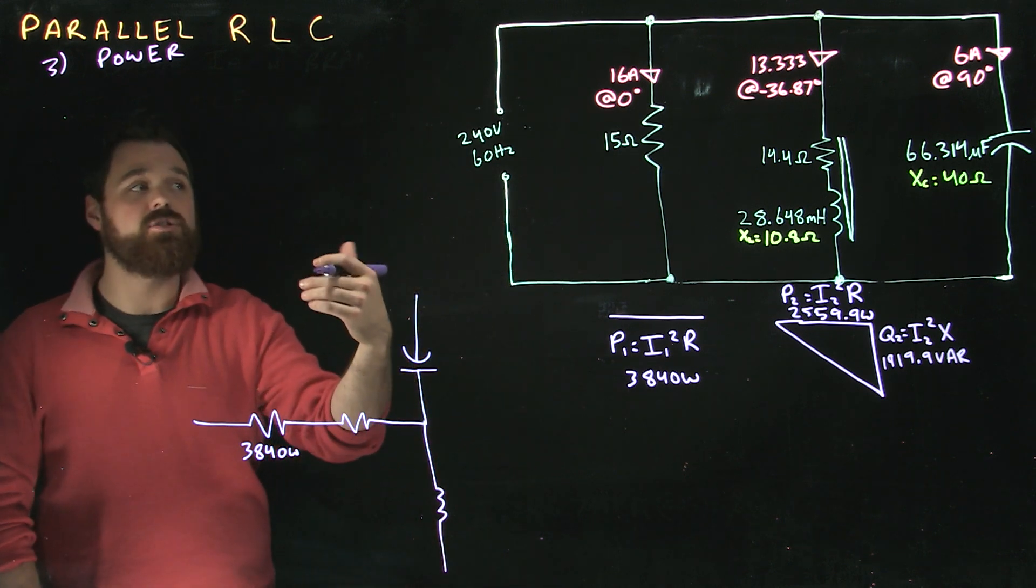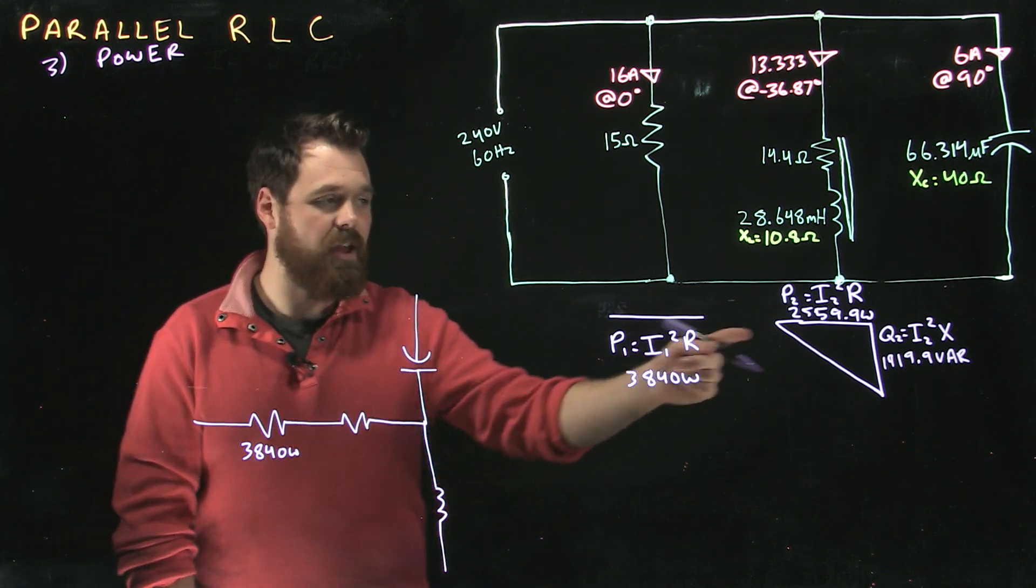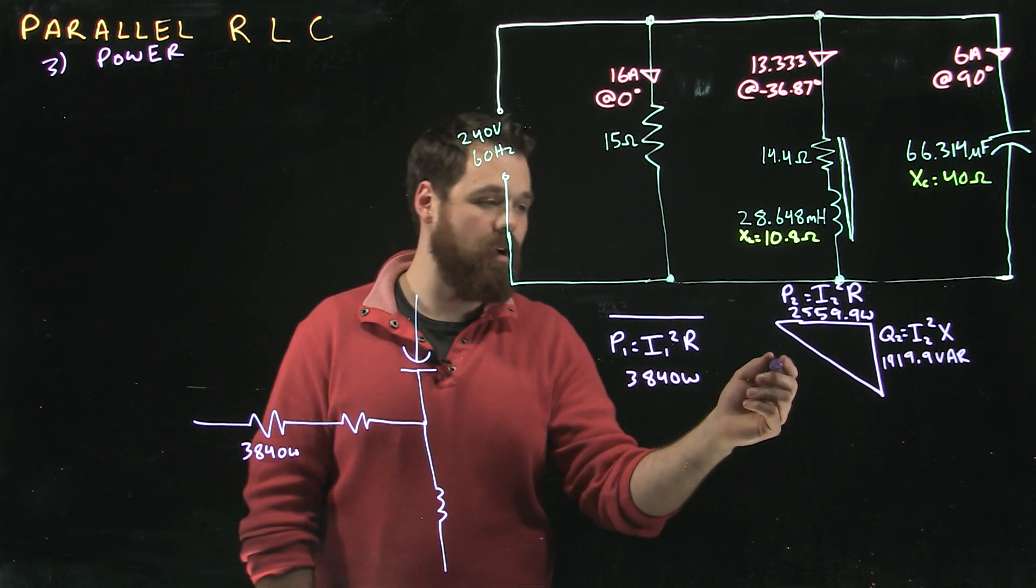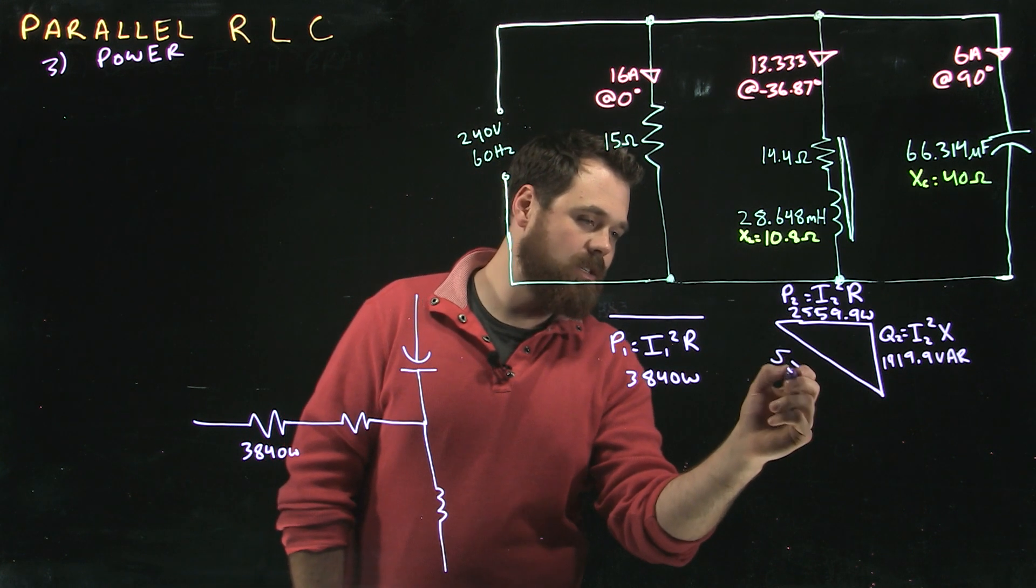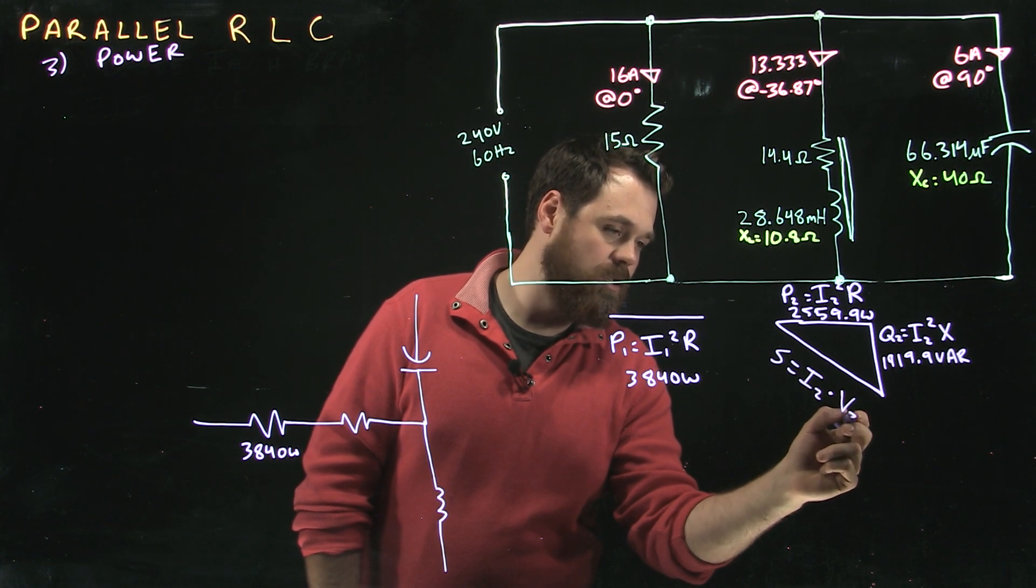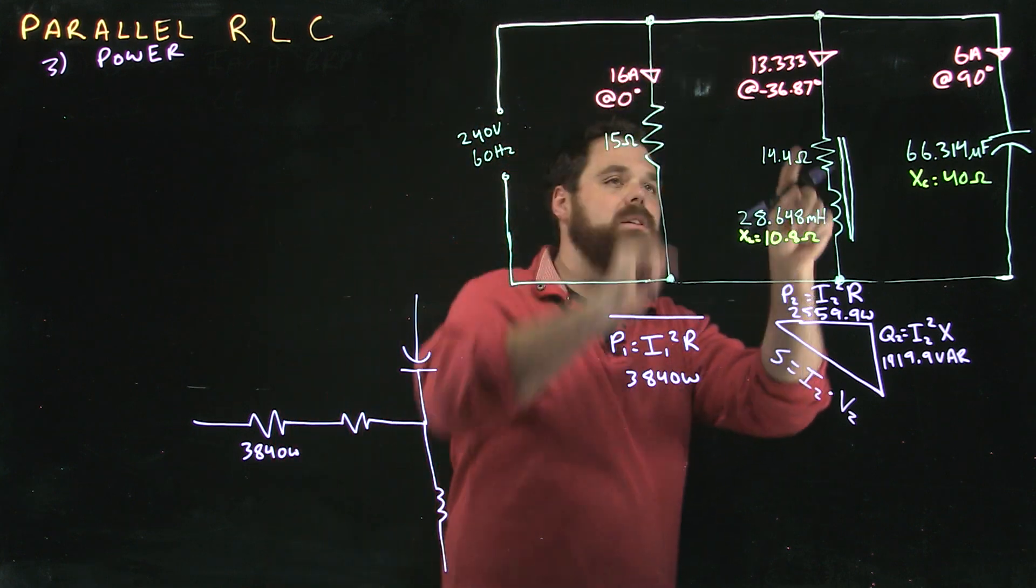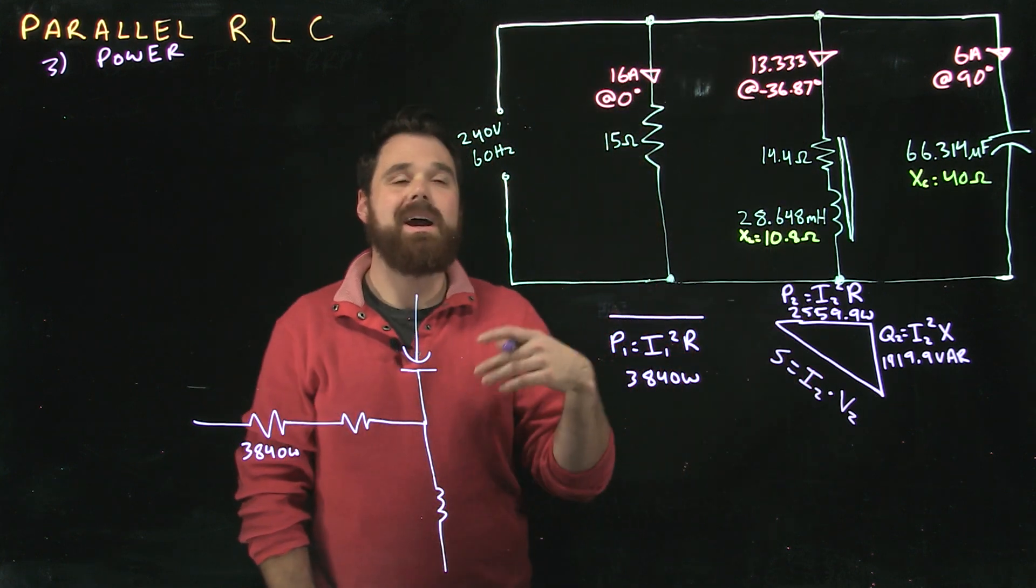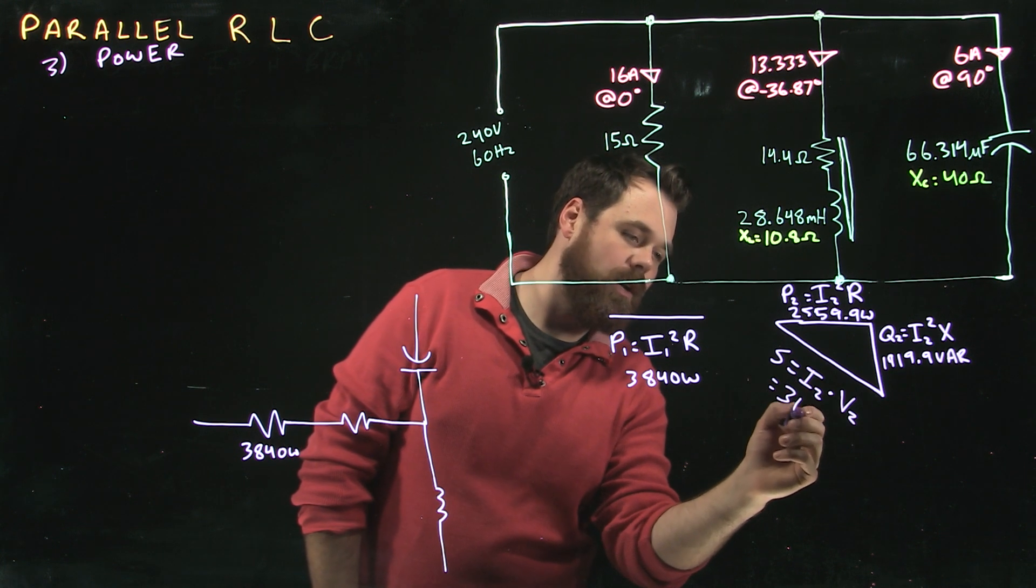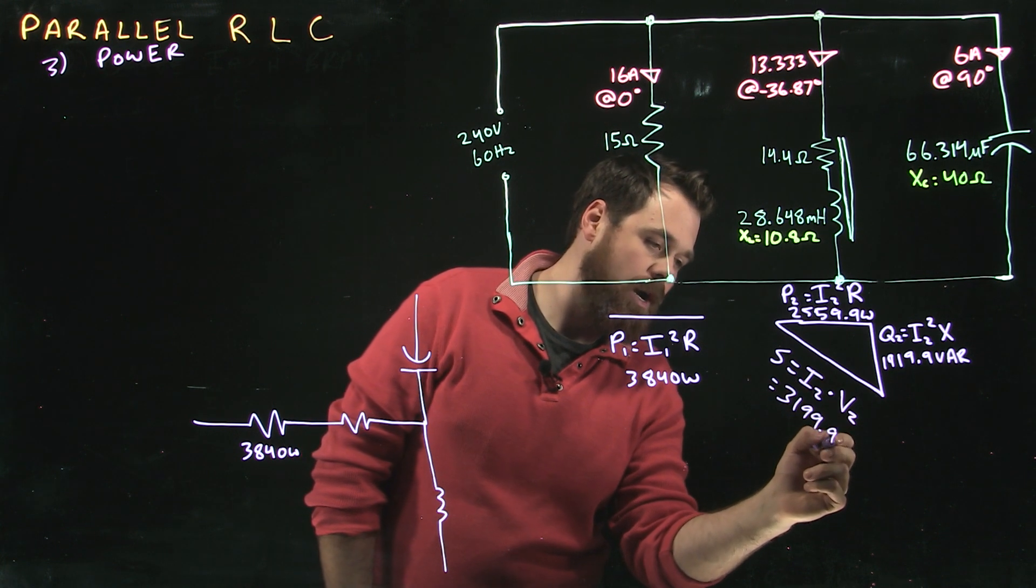Now, two ways from here. I can do some Pythagorean's Theorem. Q squared plus P squared equals S squared. Or I can go S equals I2 times V2. 240 volts times 13.333 amps. Either way, I should come out around 3199.9 VA.